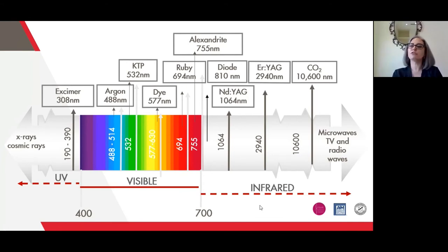That's why the first wavelength that we do hair removal is Alexandrite. And you know that Alex is considered, I guess, the most popular wavelength in hair removal. Now you know why, because Alexandrite has more absorption curve comparing to others. Shorter the wavelength, higher the absorption. The next wavelength for hair removal is diode. In majority of devices, your diode for hair removal is 810 nanometer.